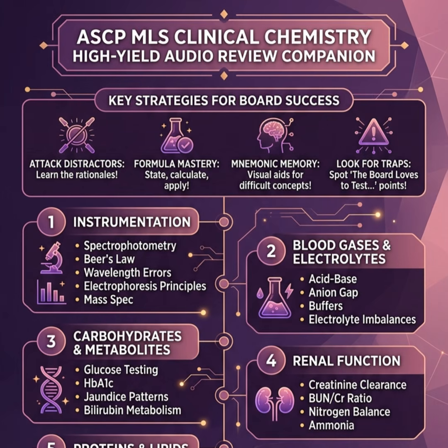It won't fit. Therefore, a properly formulated routine lipid panel reagent must contain a secondary enzyme, cholesterol esterase, to pre-digest the sample and cleave off those tails first, yielding a pool of 100% free cholesterol for the oxidase to actually work on. If that esterase component is omitted, expired, or defective, your machine will only measure the naturally free fraction, catastrophically underreporting the patient's total cholesterol by about 70%.